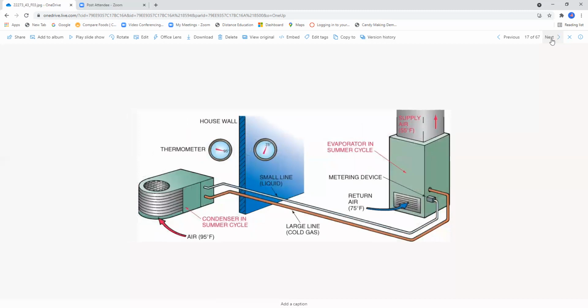Now notice that this one here is in the air conditioning mode. Now this functions as a normal air conditioner. Notice that design ambient outside is 95. Design inlet return air is 75 degrees. Of course, the evaporator coil is located here. Return is 75, and we're coming out with 55. So if you look at 75 minus 55, that equals 20 degrees delta T, which is probably the correct temperature difference for this application.